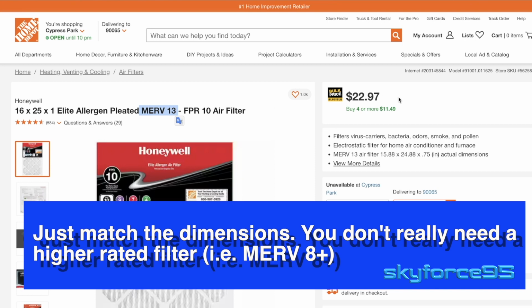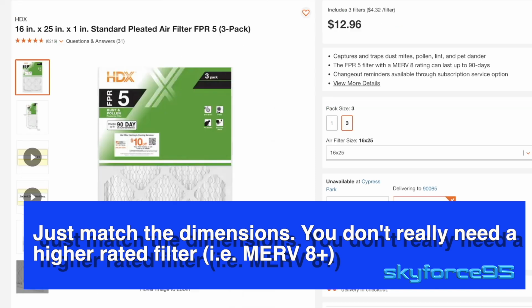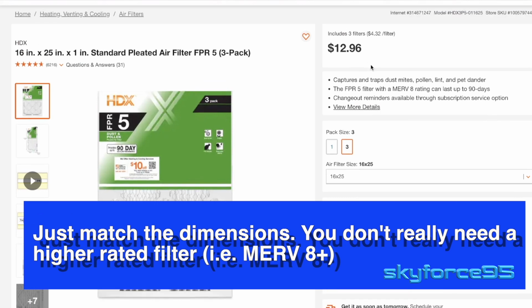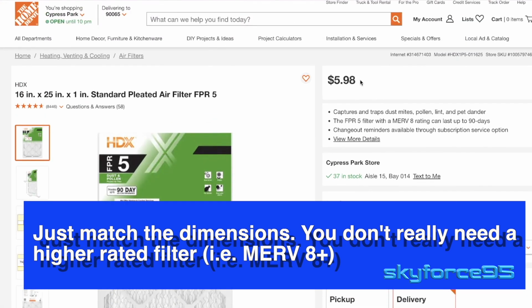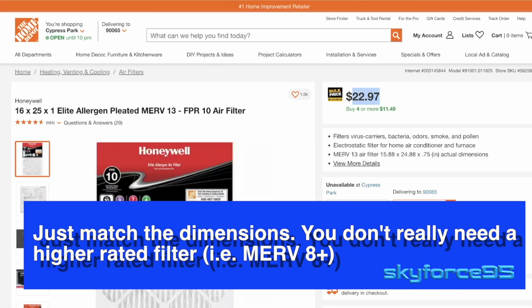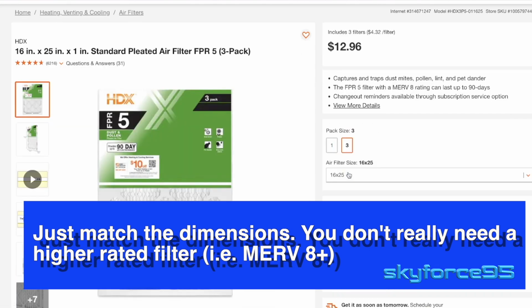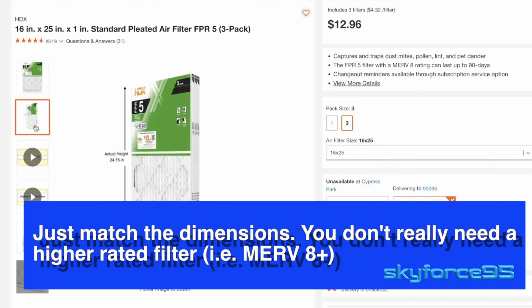Keep in mind the higher rating it has, the more expensive it's going to be, and the more frequently you may have to replace it, because higher grade filters are much finer, trapping smaller particles, so they get clogged faster. So unless you have a special case, I'd say just get the regular non-rated pleated filter.